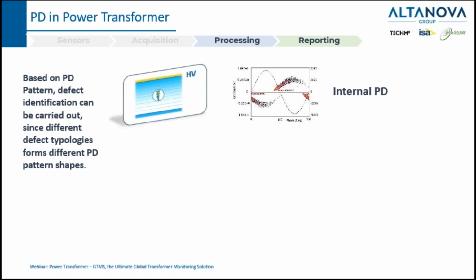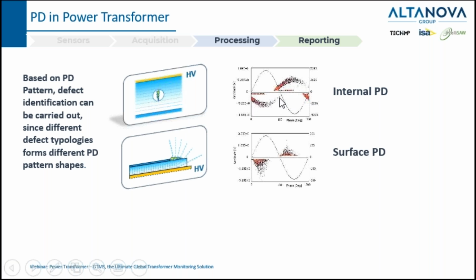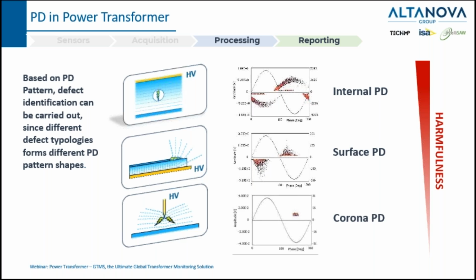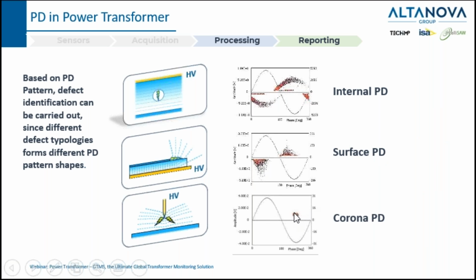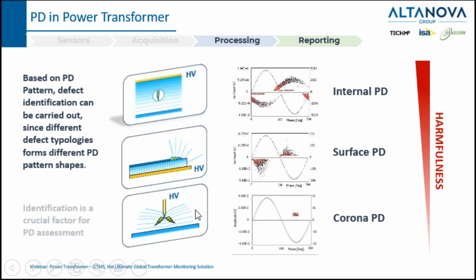I have some examples here. For example, on top you have a typical shape of internal PD, then in this case a typical shape of a surface PD. And the third and last major category is represented by corona PD, and you can see this typical representation of corona PD. Identification is important because, for example, internal PD are normally much more dangerous than surface PD, and in general, surface PD are more dangerous with respect to corona discharges.